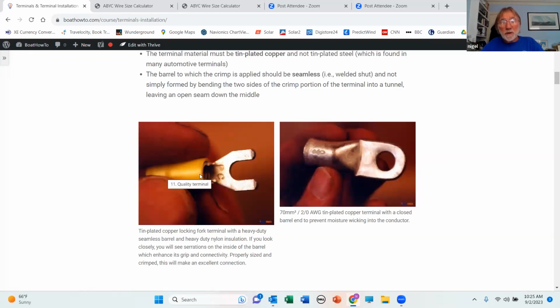Again, if you buy a cheap terminal, it's just two bits of metal that have been folded over like this. And when you crimp down on it, it can open up and make a lousy terminal. So we want the barrel to be welded shut. And then inside of the barrel, we want little serrations on here because that helps to grip the terminal when you crimp down on it. So there's a lot of features to a quality terminal that you will not get, including longer barrels. So you've got more of a contact surface area and you're less likely to screw up the crimping. And these kind of features you're not going to get if you go buying your terminals from Amazon. Not unless you look for quality terminals on Amazon.